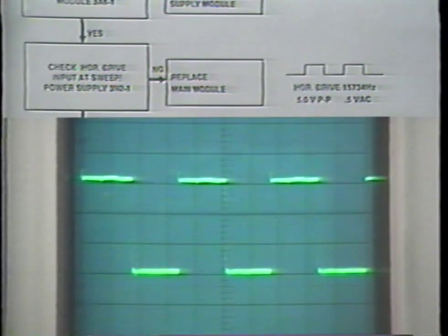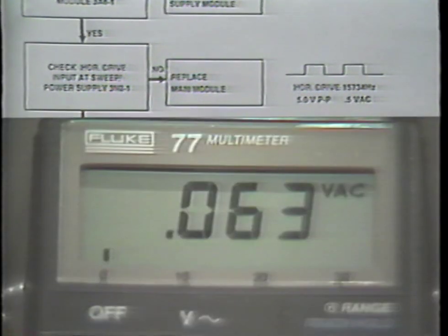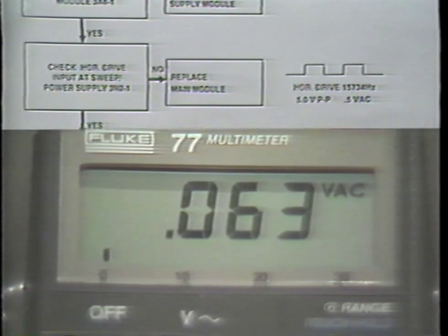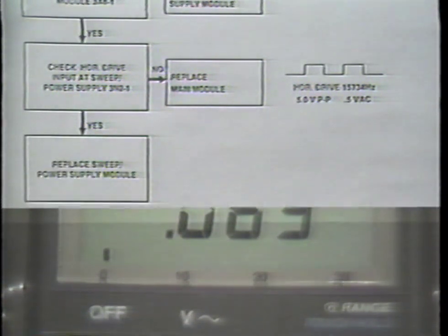On the scope, we will see our drive waveform, which should be somewhere between 5 and 6 volts peak to peak. In the field, using a meter, the reading will be quite low; we just want to determine whether there is sweep drive. If there is no drive, replace the main module. If drive is available, replace the sweep power supply module.